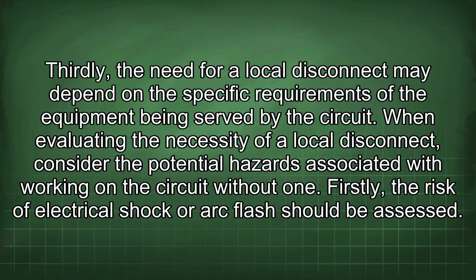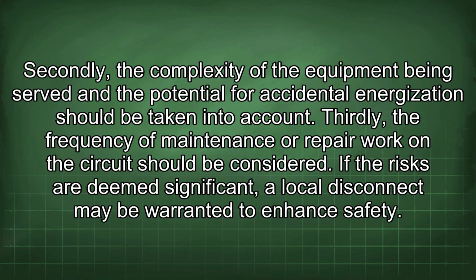Firstly, the risk of electrical shock or arc flash should be assessed. Secondly, the complexity of the equipment being served and the potential for accidental energization should be taken into account. Thirdly, the frequency of maintenance or repair work on the circuit should be considered. If the risks are deemed significant, a local disconnect may be warranted to enhance safety.